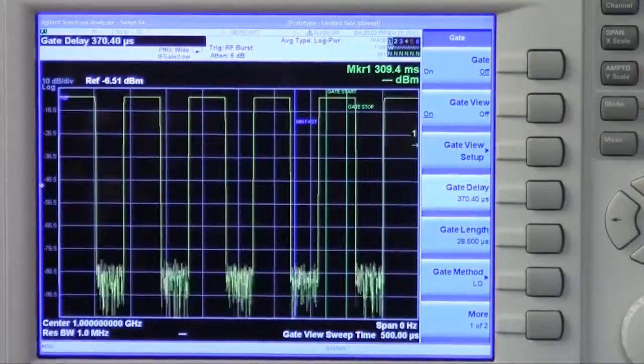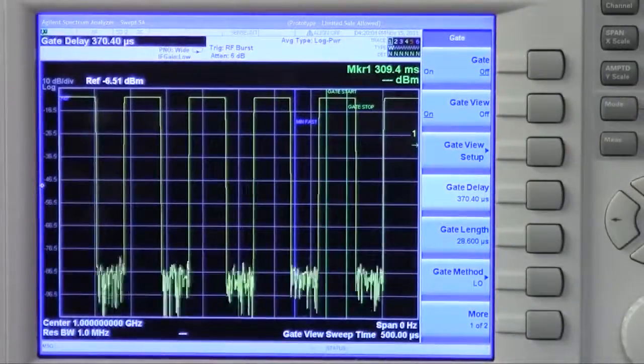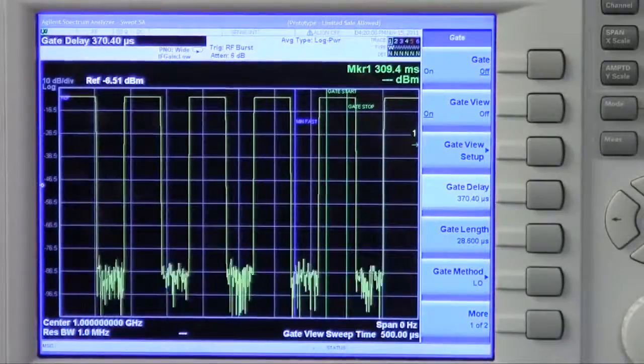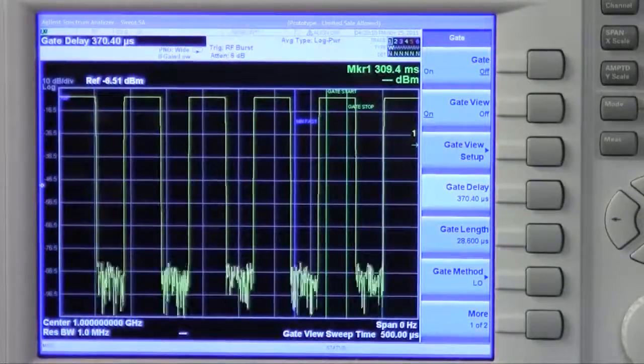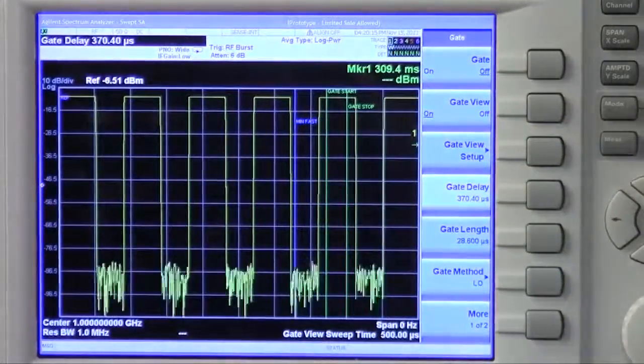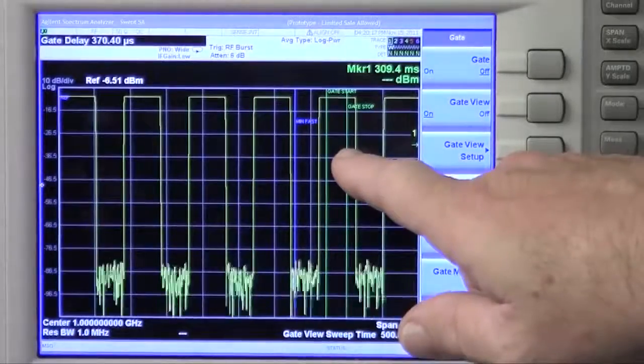If you try to set the gate delay lower than that, you have to use a much lower sweep time to overcome transients in the system. So you really have to use min fast as the minimum value for your gate delay time.